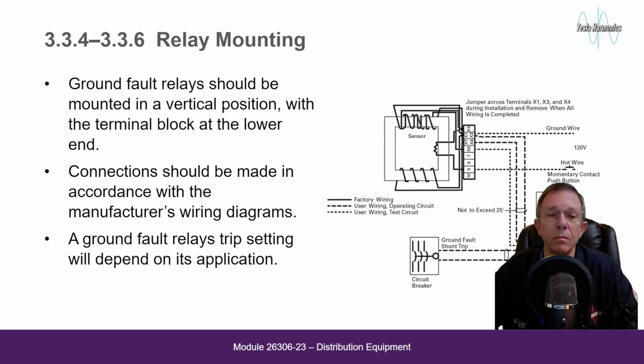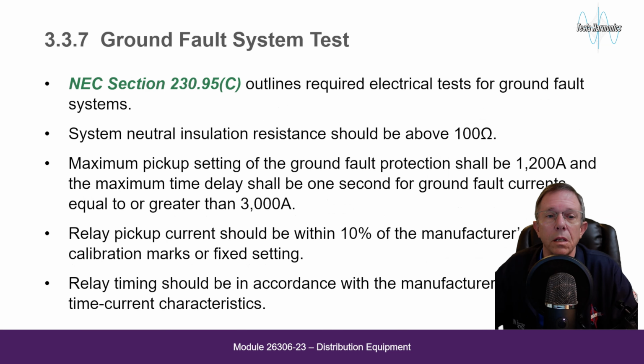Relay mounting. Ground fault relays should be mounted in a vertical position with the terminal block at the lower end. Connections should be made in accordance with the manufacturer's wiring diagrams. A ground fault relay trip setting will depend on its application. Ground fault system test. NEC Section 230.95C outlines required electrical tests for ground fault systems.